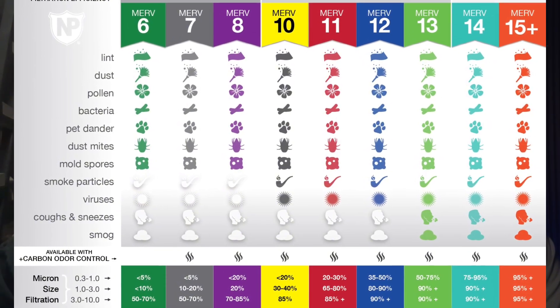These filters have to be designed into the system. Countless times a homeowner with allergies goes to the big box store and sees the 'allergy buster' — good for pollens, mold, spores, dander, and dust mites — and thinks it has to be good. They pull out their one-inch filter, put the allergy buster in, and yes, it will filter fantastically. But that Goliath, the giant slayer, will kill your air conditioning system.